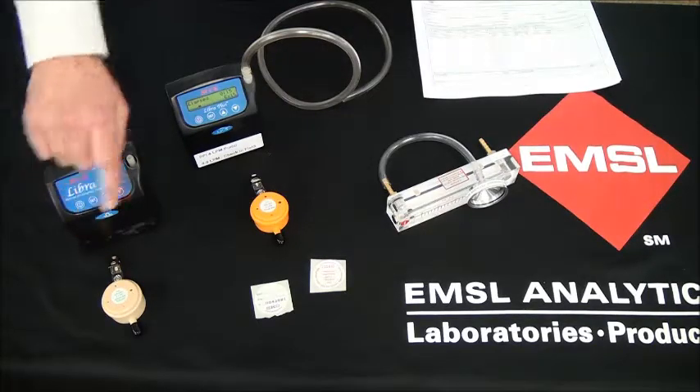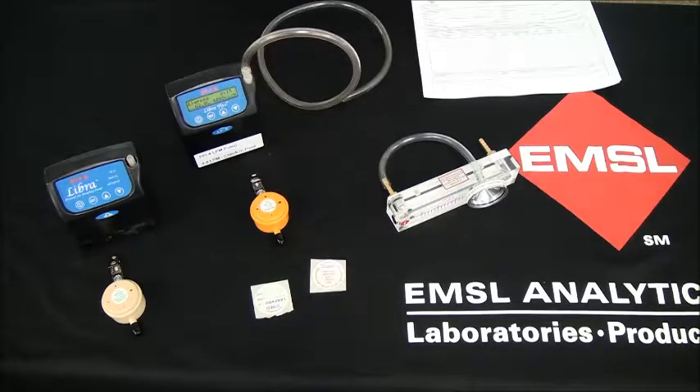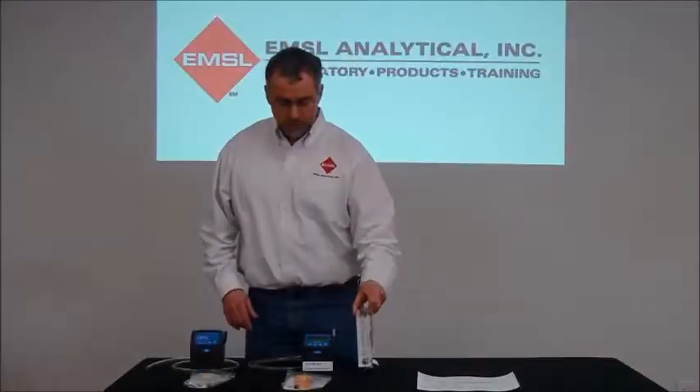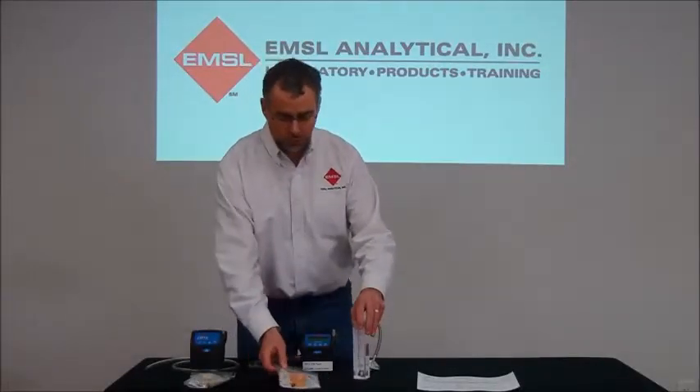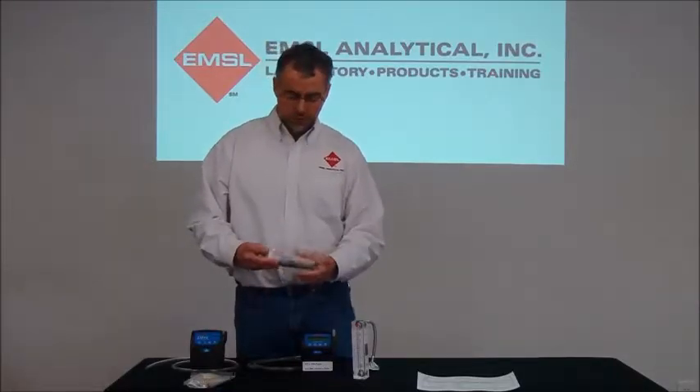PPIs are available in either a 2 liter per minute, a 4 liter per minute, or an 8 liter per minute model, along with a rotameter with a calibration adapter. In this case, we ordered a 4 liter per minute PPI, which was laboratory loaded with a pre-weighed filter cassette.